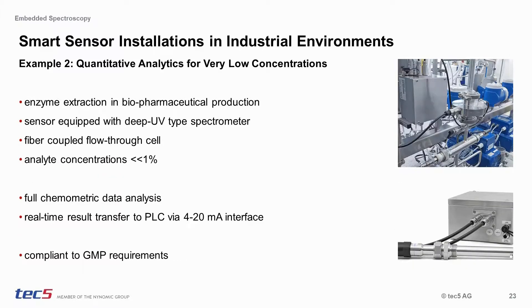Our second application is another example using a UV-based smart sensor in liquid phase, this time using a fiber-optic-coupled flow-through cell. UV spectroscopy is an extremely sensitive and specific detection method; with its typically very high extinction coefficients, measurements even at very low concentrations are feasible. In this application — a pharmaceutical separation and purification process — the concentration range has been far below 1%. In contrast to example number 1, a full chemometric data analysis has been applied and the results were transferred in real-time via a 4 to 20 mA interface.